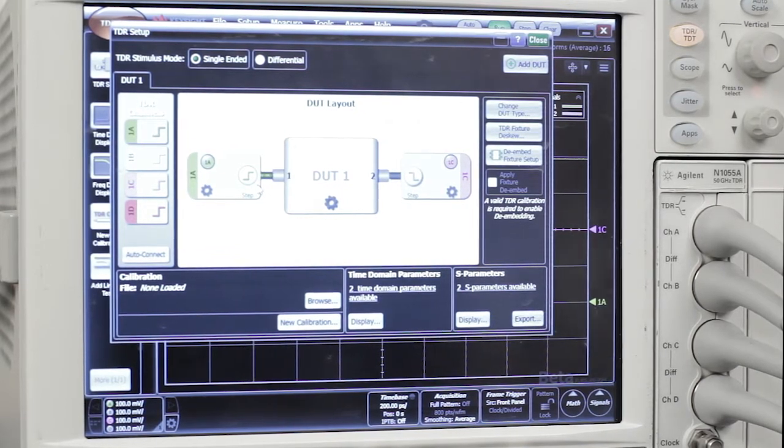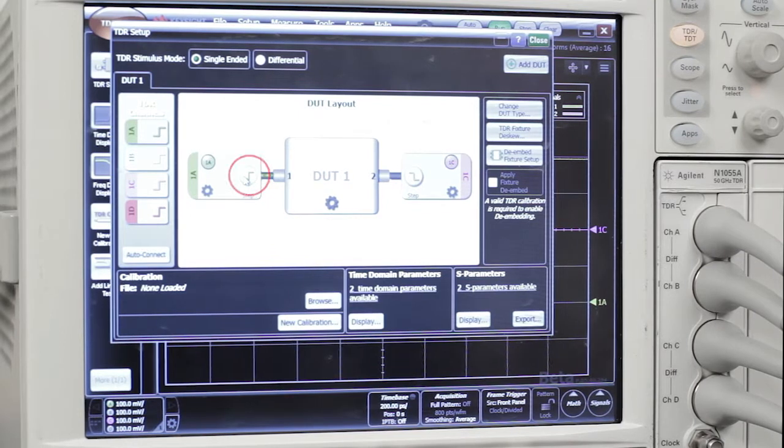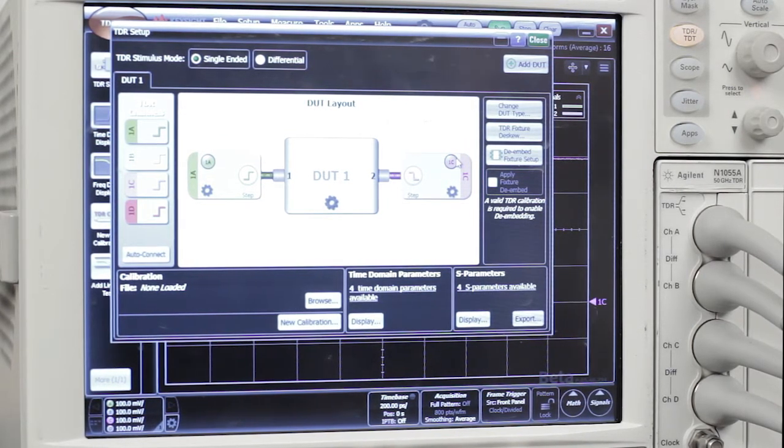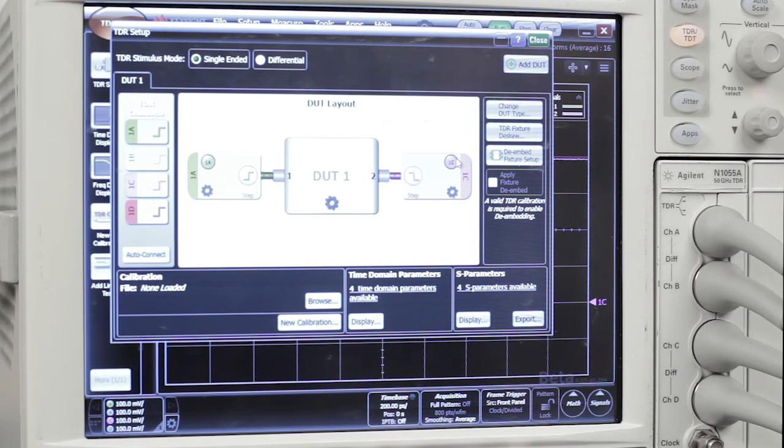At this point, you're ready to make measurements with your TDR. You can turn the steps on and off with these controls. You can turn the receivers on and off with these controls. But if you want the best accuracy and if you want to be able to use advanced features like AFR and de-embedding, you need to perform a TDR calibration.